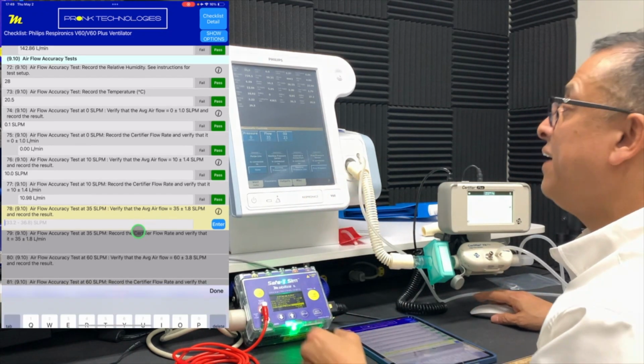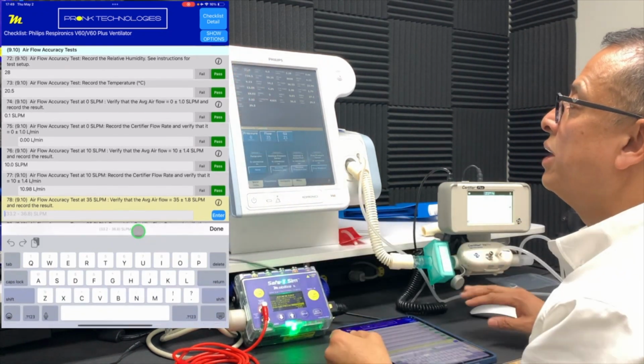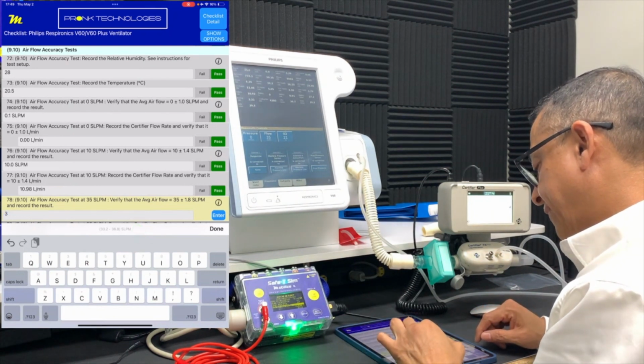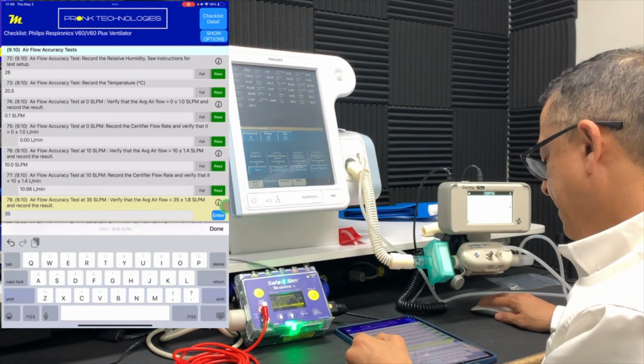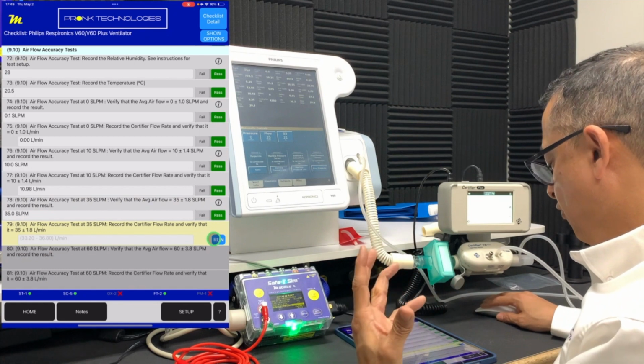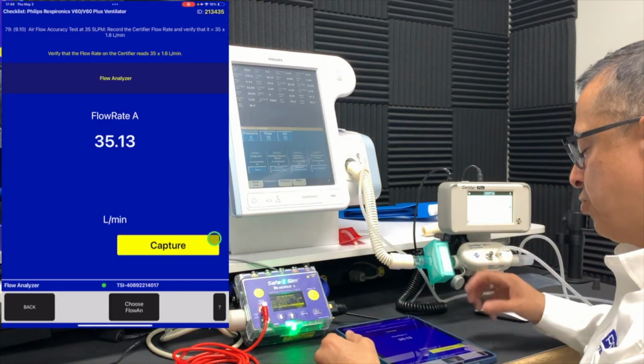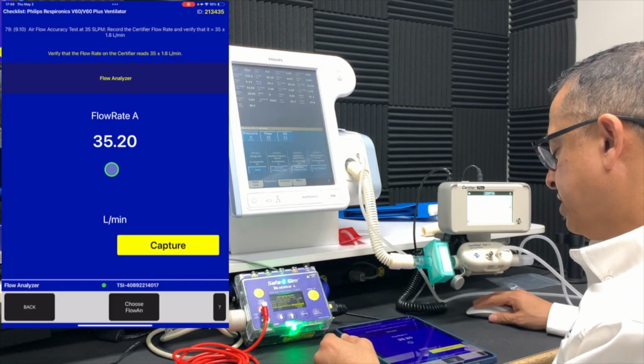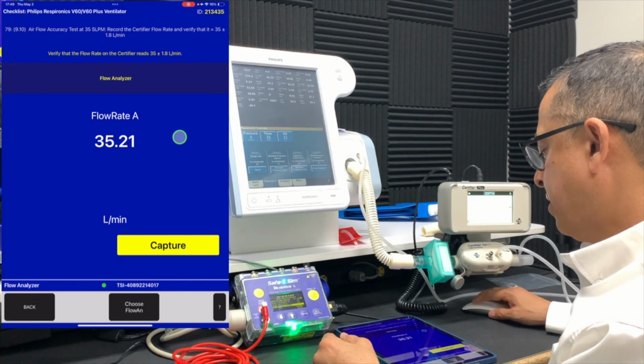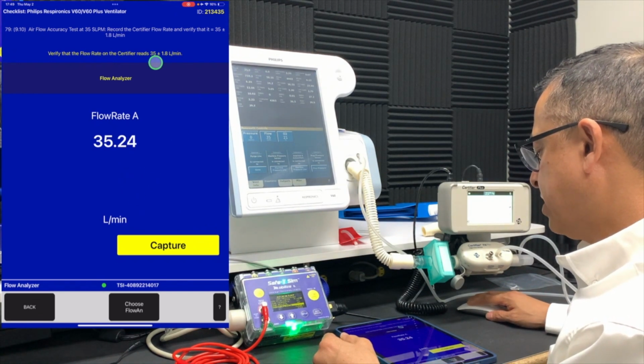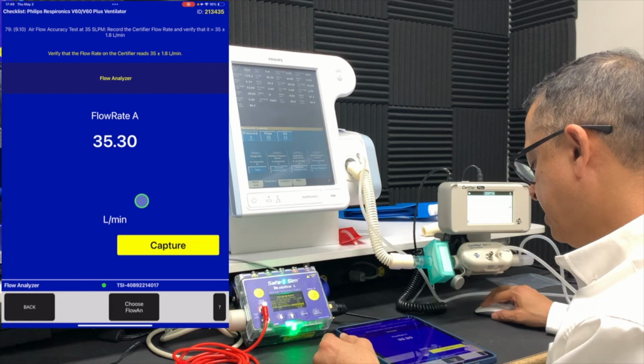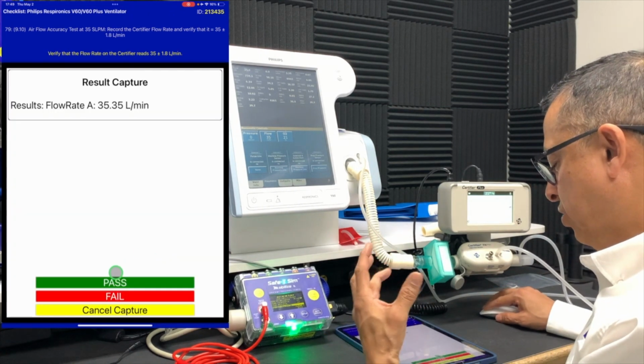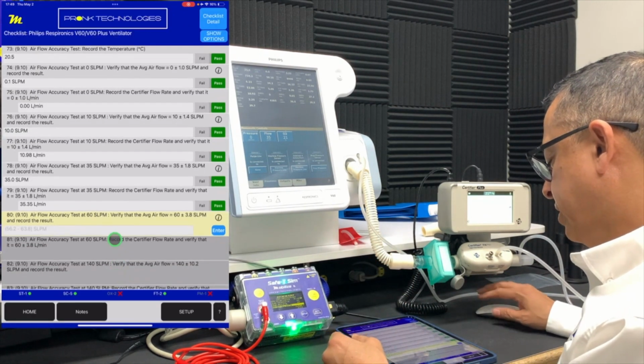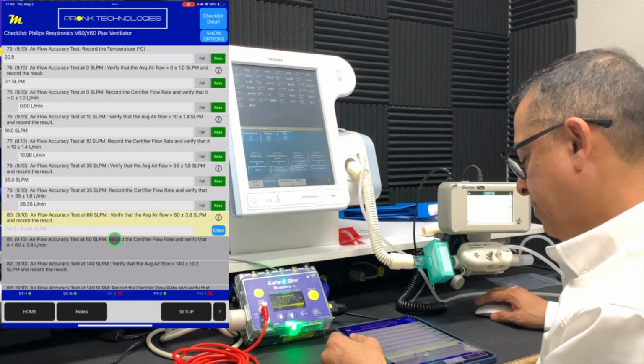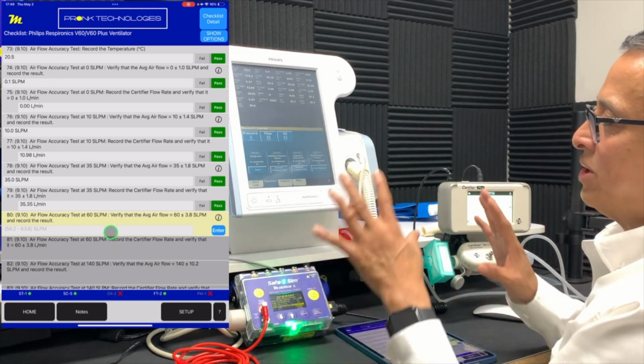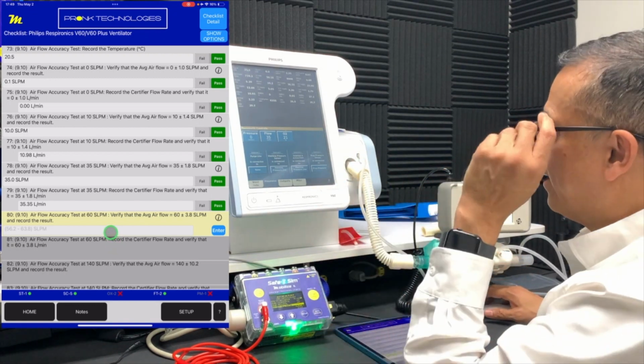So at 35, our ventilator is actually putting out exactly 35. We'll capture that. And then same thing again, using the certifier to confirm the measurement and confirm its accuracies within specification. You can see here at the top, the procedure tells you what the tolerance is for that particular test. So as a technician, you always want to do your verifications. You want to utilize your skills to make sure you can verify that the device is performing properly.